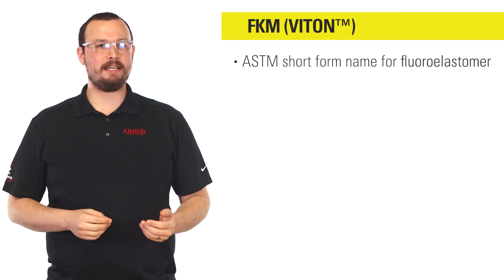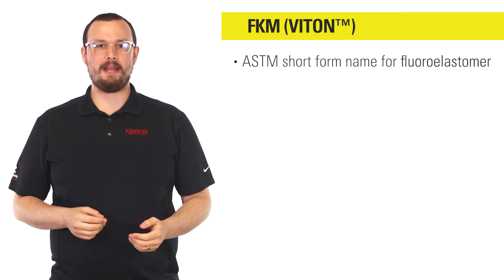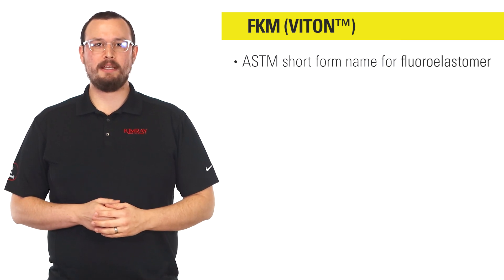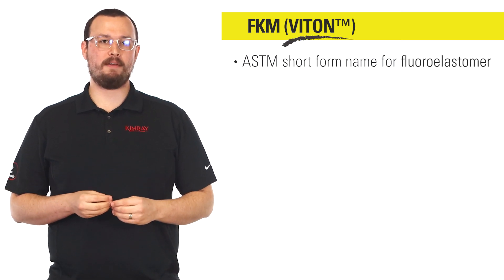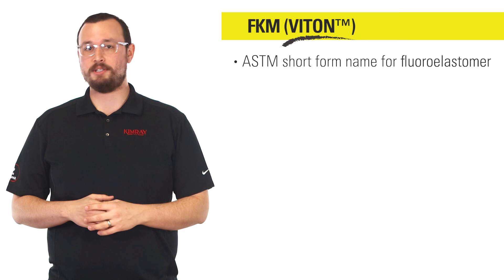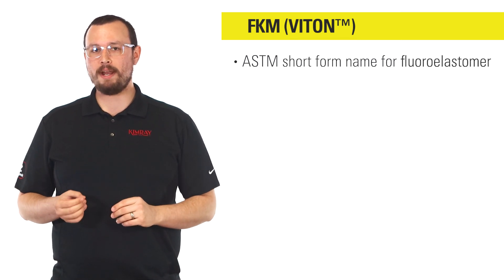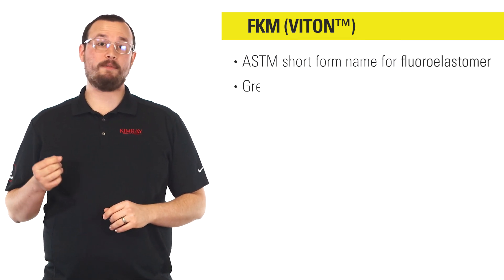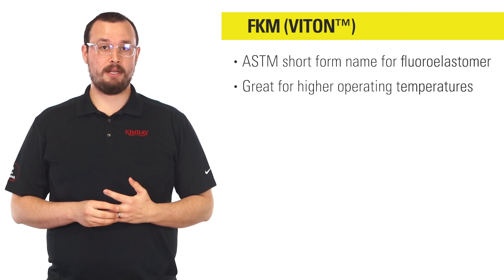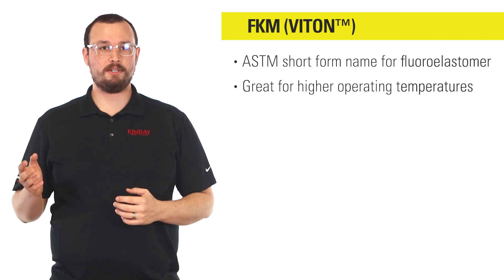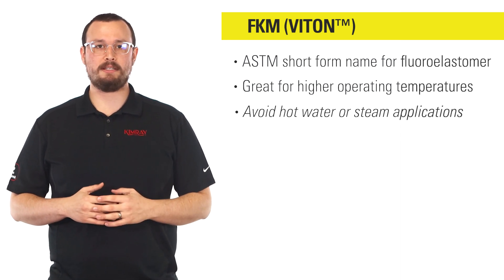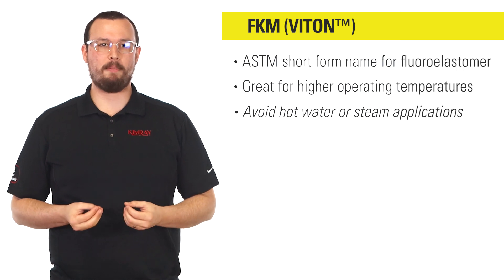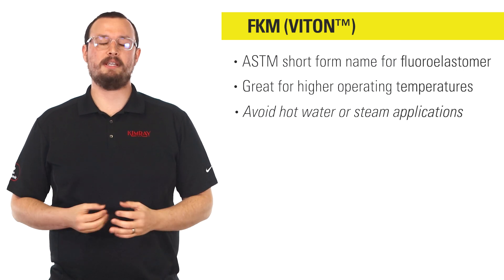FKM is the ASTM short form name for fluoroelastomer. Kimray uses Viton, which is a registered trademark of the manufacturer but also widely used for the material in general. Viton is a great option primarily for higher operating temperatures. However, with those high temperatures you'll also need to avoid hot water or steam applications, as the material will quickly break apart under those conditions.